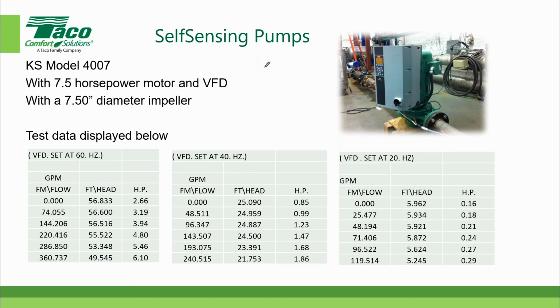If you want, by the way, if you specify a self-sensing pump, you can have it certified, and that means that we would take it off the assembly line and put it physically in the lab. There's an extra cost for having the pump certified, and some people not only want it certified, but they want it witnessed. A witness is the same as a certification test, only someone sends a representative to the factory to witness the actual certification. And we actually give them a certified curve that says the pump operates in accordance with the measured data in the laboratory.